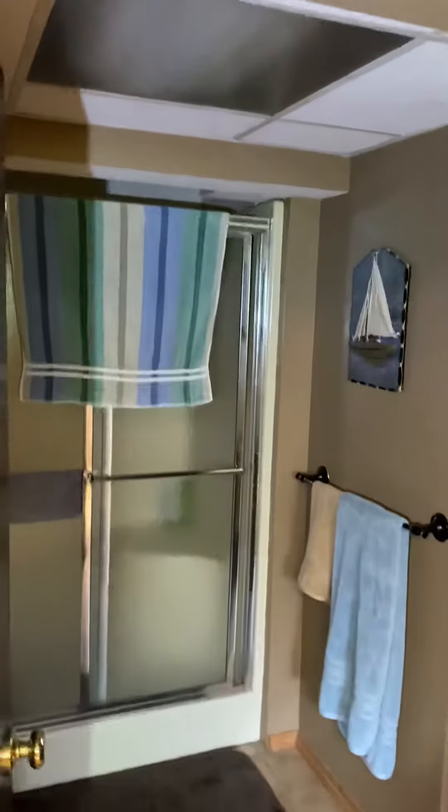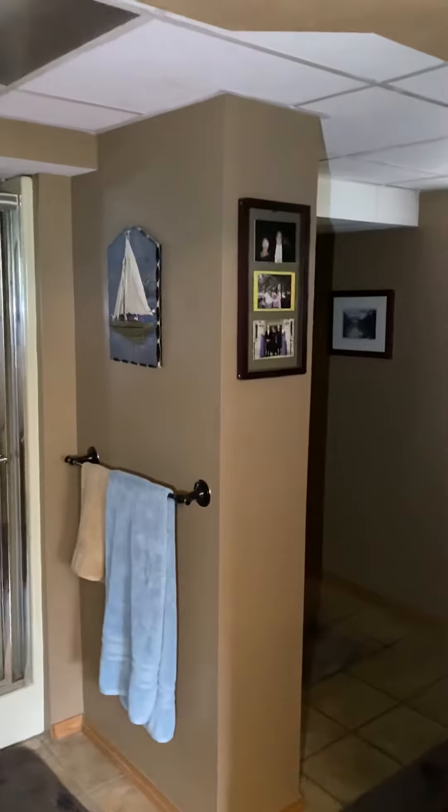The Freon lines run up. Looks like they're going through a finished ceiling, heading over this bathroom next to the beam there. I would just fish the Freon lines to change them out.